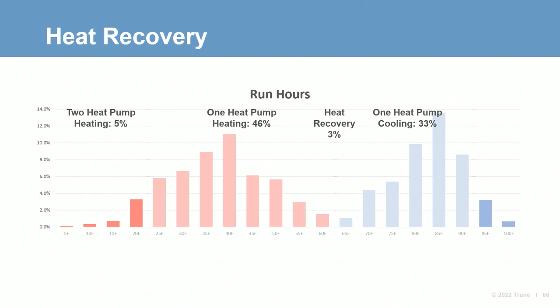Recall our table showing that simultaneous heating and cooling loads between 55 and 60 degree outdoor air are only 3% of the annual run hours. Air-to-water heat pumps perform at a high efficiency in this mild temperature range, which means that a dedicated heat recovery chiller may have a relatively small efficiency benefit. However, a properly sized dedicated heat recovery chiller can eliminate the need to operate two air-to-water heat pump units and their associated pumps, with both units at low loads to meet the simultaneous demands. This can extend the life of the air-to-water heat pump units, as well as provide some system control and efficiency benefit. Note that the size of the heat recovery chiller to provide this benefit is quite small, approximately 18 tons in the school example.